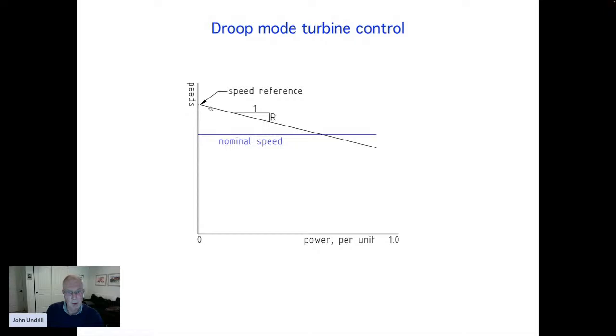Its job is to make sure that the speed of the turbine, which is, of course, the same as the speed of the generator, is related to the power that's developed by this drooping line. If every owner of every generating unit on the system agrees to operate according to this rule, you have very effective control of the system.